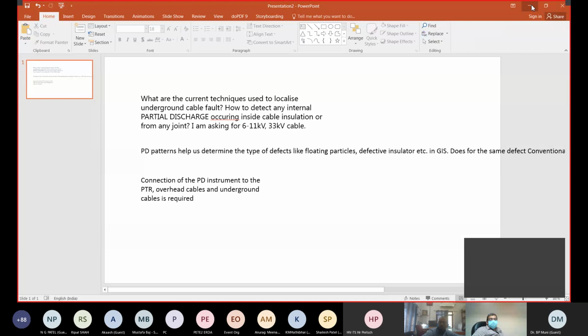One big advantage is to change the frequency. That means if you have a resonant test frequency, for example, if your GIS or the cable is directly connected with an air insulated substation or power line, and maybe the substation around is still in operation, and maybe you have a lot of external PD at 50 or 60 Hertz, then if you have another frequency, clearly you can definitely extinguish external noise. That's one big issue and one advantage of the resonant test system.